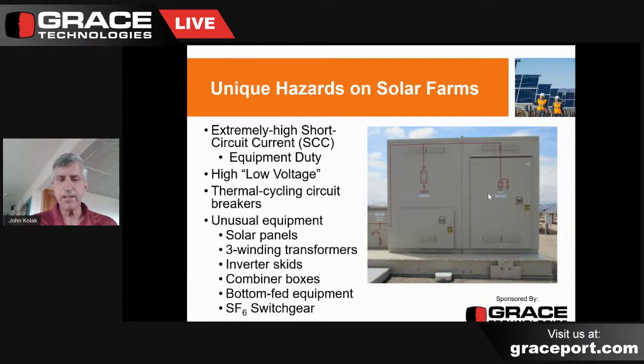And then finally, sulfur hexafluoride switchgear, SF6 switchgear. There's a unique kind of switch that often exists on these solar farms, and it is exactly the same switch that you'll see on wind turbines when the transformer is actually up tower. So you'll find this sulfur hexafluoride switchgear that they work on. They require special training to make sure they're functional to use, and they also have lockout tagout implications that I really won't go into here.